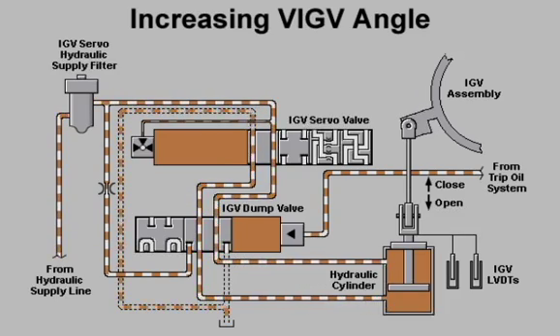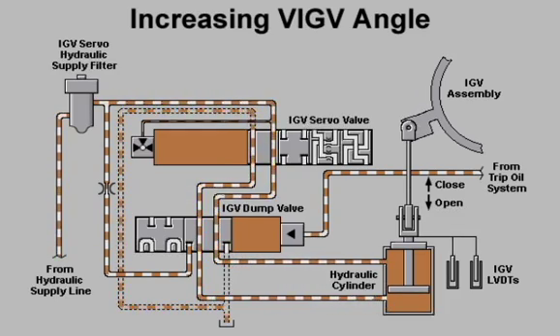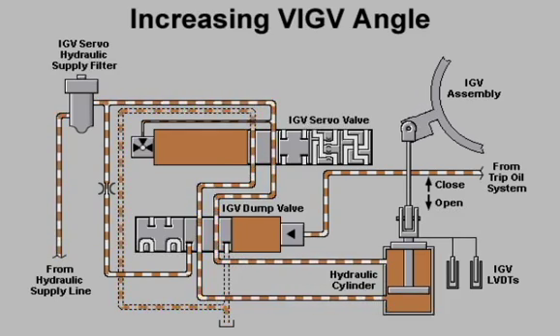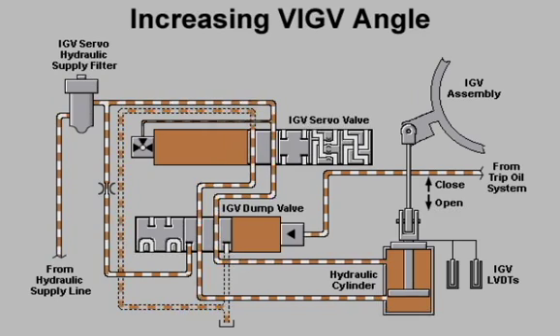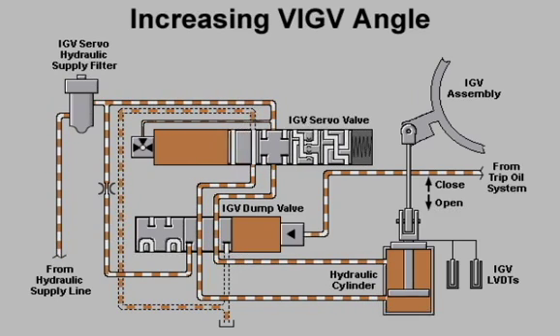The actuating arm of the hydraulic cylinder retracts and rotates the inlet guide vane ring counterclockwise, turning the variable inlet guide vanes to a greater angle.